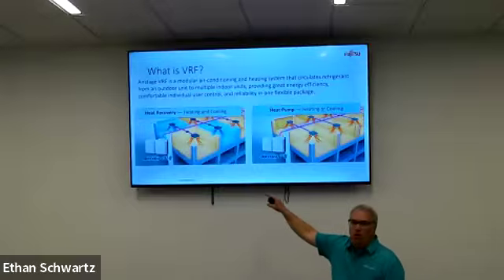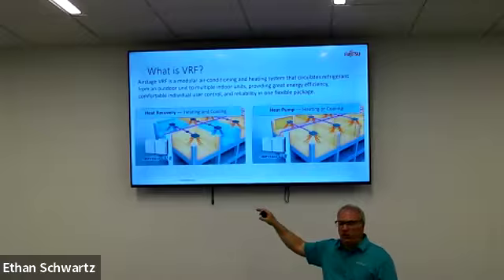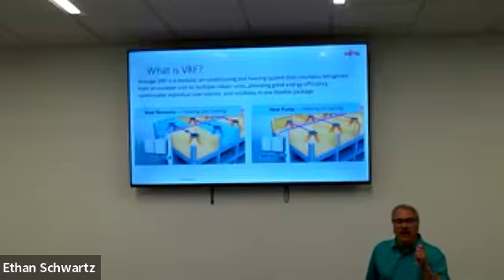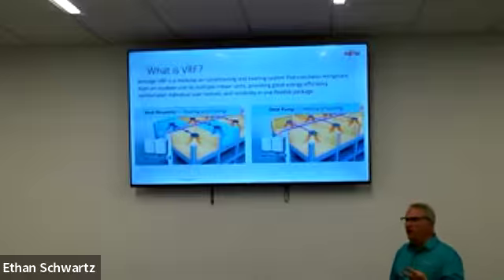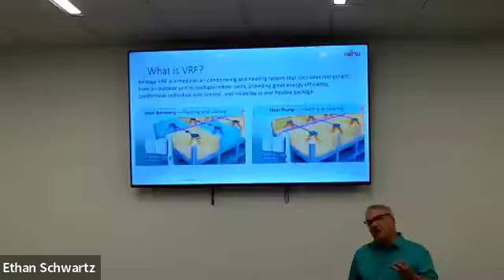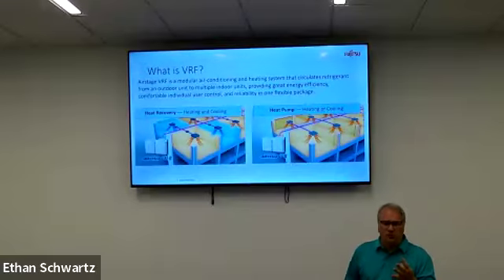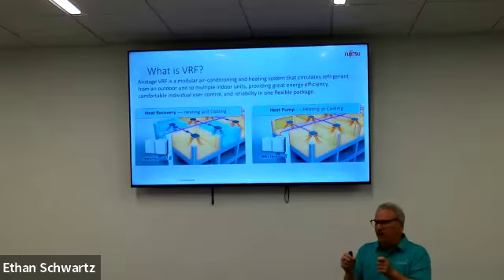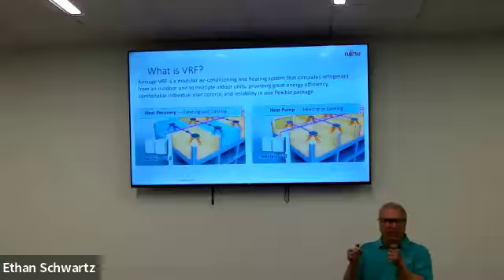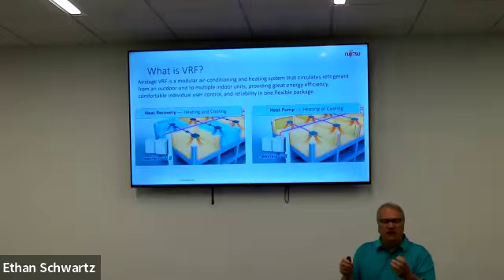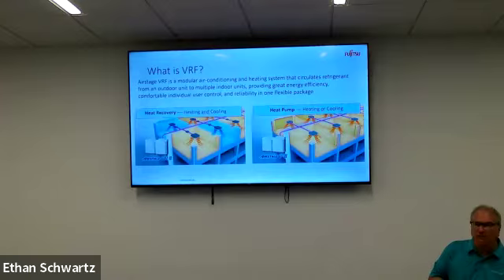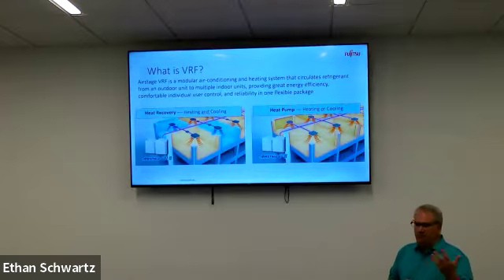So be sure as you're talking with the customer what you want to have. And if it's an occupancy like a hotel or multifamily residential, not so much dormitories, not so much nursing homes, because the expectation of the occupant isn't to have that specific selection when they're in that room or that zone to make their choice. Me, last year was 82 nights in hotels. And there's sometimes I walk in, and my personal physiology, whether I'm under stress or whatever, I want it to be cold, so I want it to be in cooling.